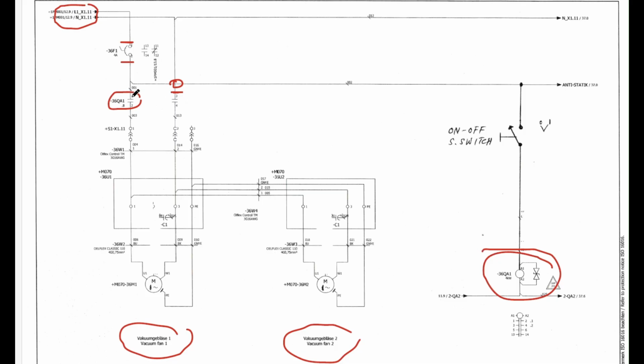Suppose we connect here at number 1 and we are getting voltage. But when we connect the red probe at number 2, we don't get 120 volt. It means we have an issue, because this contact is normally open, and it must be closed. How will it be closed? As soon as this contactor is energized, this contact closes and supply will pass. Remember, this contact also belongs to this contactor. Then we'll leave it here, because we verified that supply is okay up to terminal number 1, but we are not getting supply at number 2.